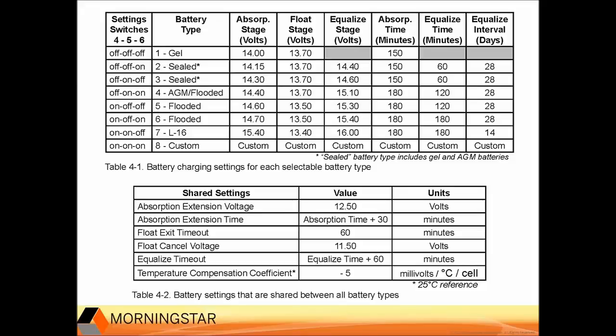In solar battery systems, it drops out of float every night, and if the battery is cycling, these higher float settings can help give the batteries a bit more charge after absorption. Grid-type battery backup is one of those applications where it can sit and float for months on end without getting cycled. In those situations, the inverter charger will settle at the lower float voltage, but the controller will stay in bulk charge mode and not reach float until there is an outage. That's where these higher float settings can possibly be a better choice to keep the batteries as full as possible.